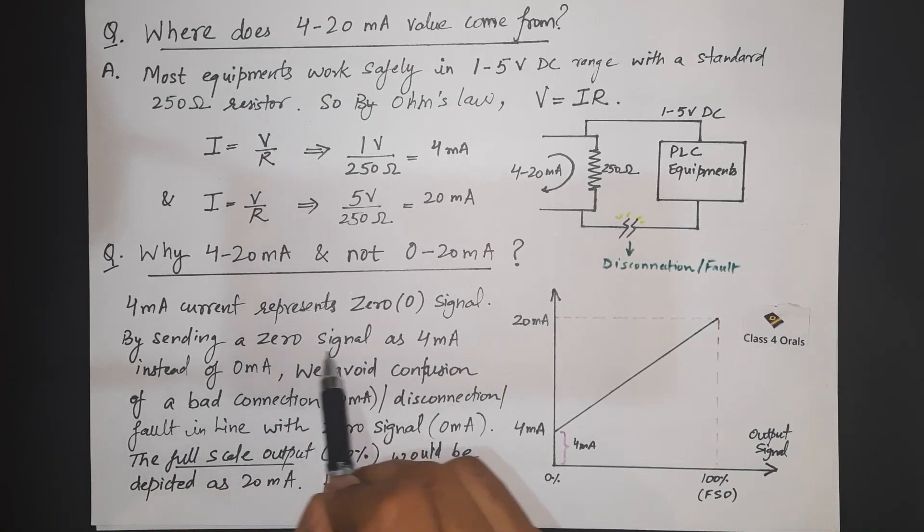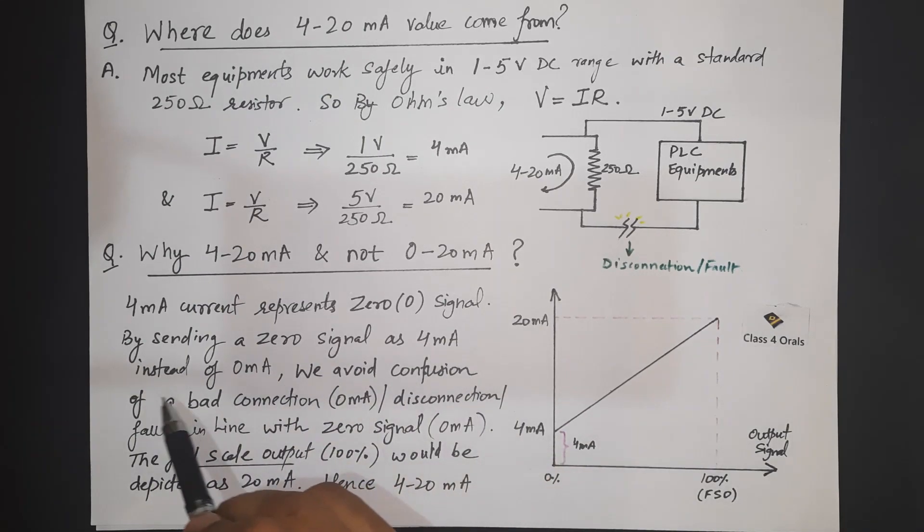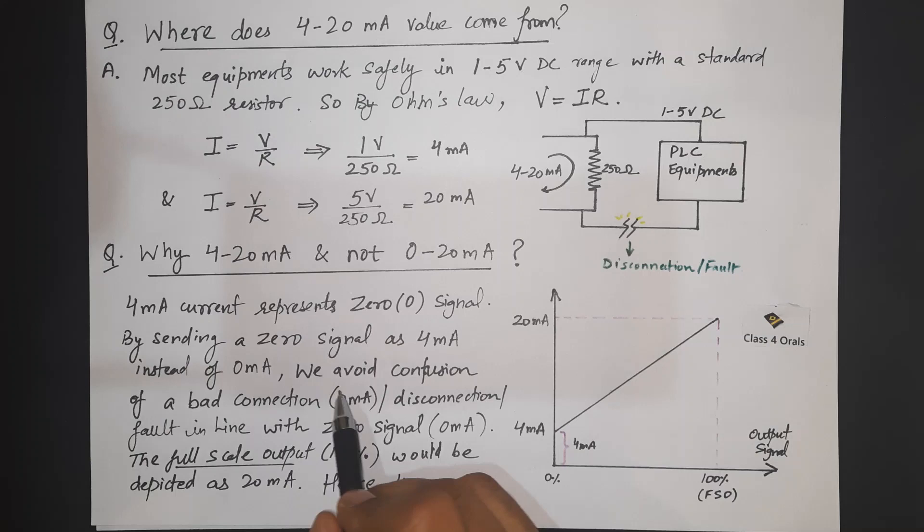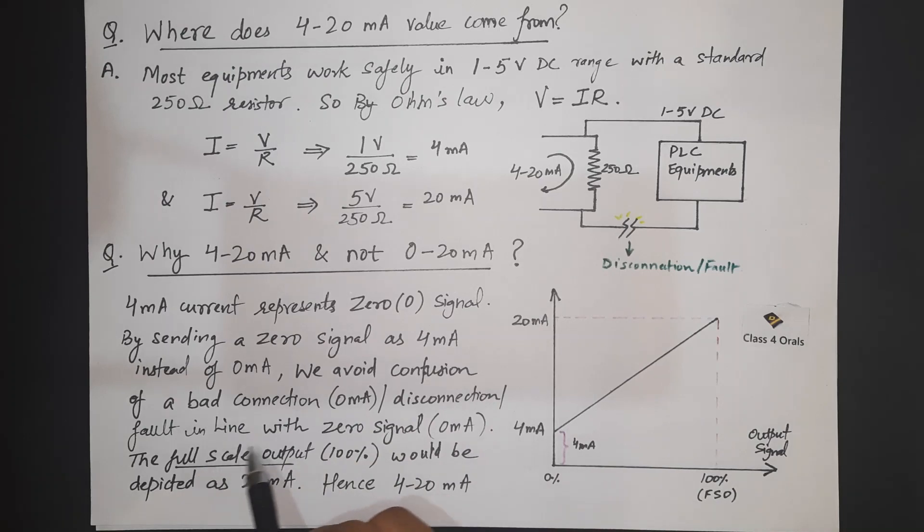Because the answer to this question is the 4 mA current represents the zero signal. By sending a zero signal as 4 mA instead of 0 mA we avoid the confusion of a bad connection.